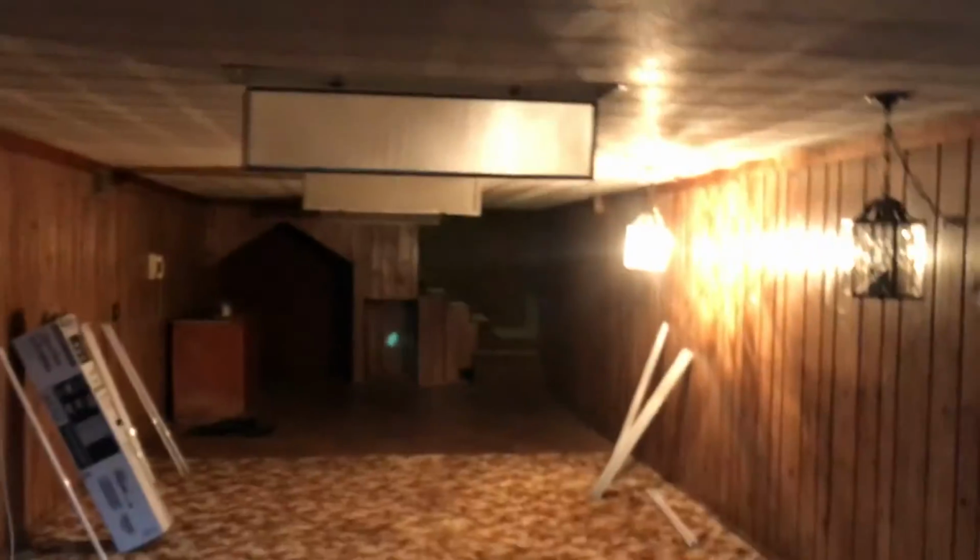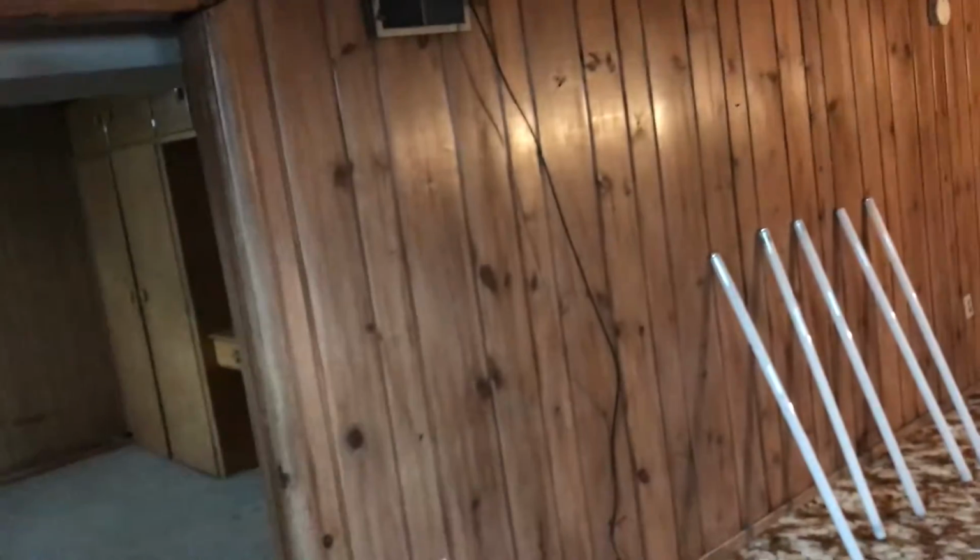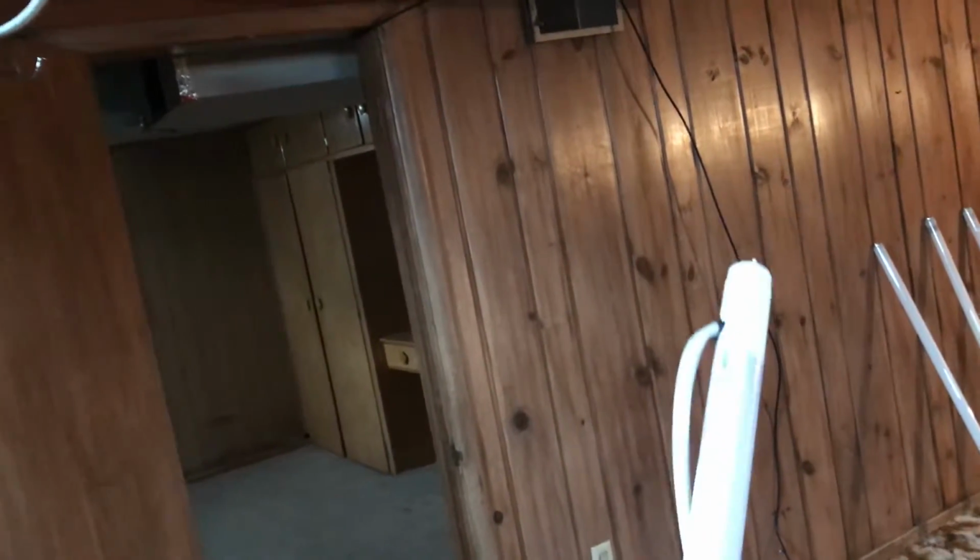We've taken our LED lights, which are these right here. You can see the T12 pin pattern right there. Now, those things are nothing more than handles that hold the lights in. No electricity runs through them. They're just plastic. Electricity runs through this wire here that we're going to hook to the wire source coming in. Anyway, so we've done that here.